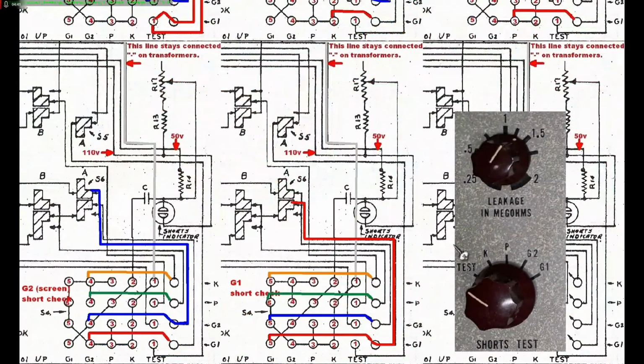So if there's a short, we get an indicator, a short's indicator there. And so on, the same thing through grid 2 - grid 2 connects everything to the number 4 position. And so on with grid 1, connects everything to the number 5 position. So you have the shorts test mode when you're testing the tube for operation: cathode, plate, grid 2, grid 1.